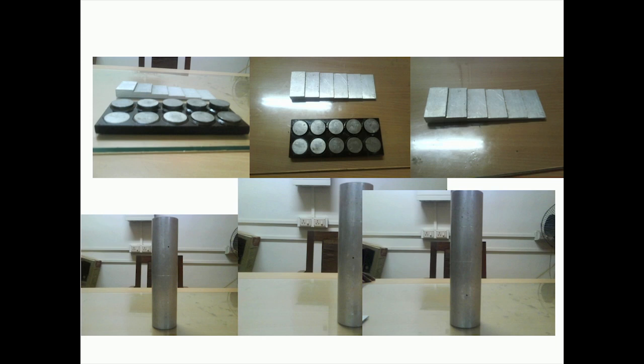Okay. So like this, you can make this kind of artificial flaws on these reference standards or standard blocks. And since the location and the depth of these defects are known, you can get an echo from each of these defects and then see on the display screen whether that echo is coming at the place, or at the time, where it is supposed to come. Okay. So like that, by collecting the data at different depths, you would be able to calibrate the instrument.